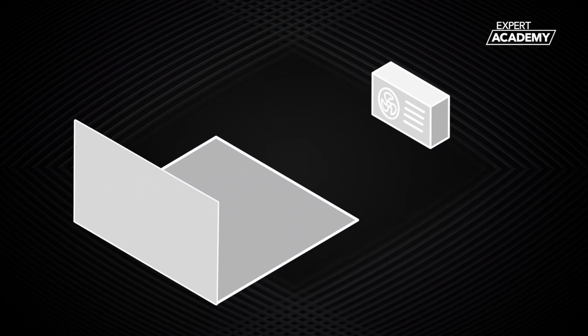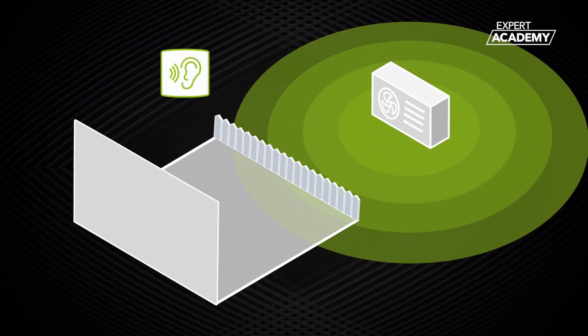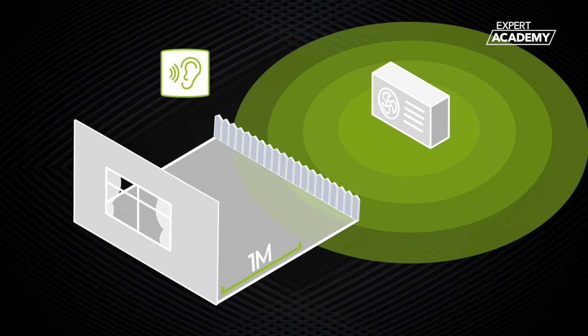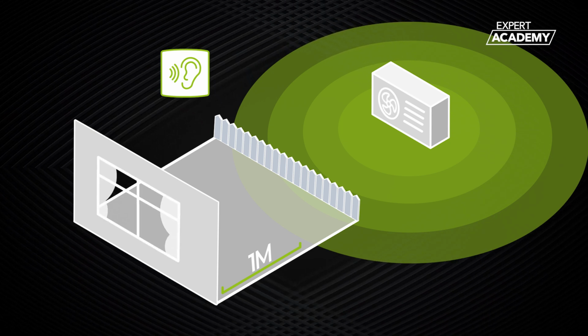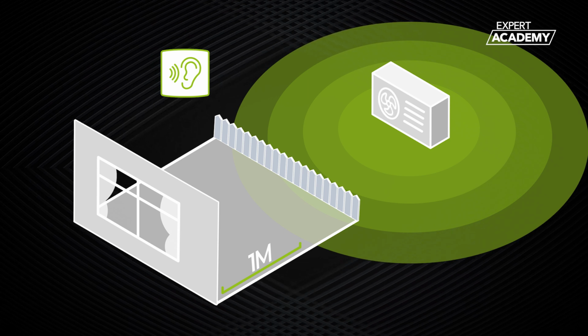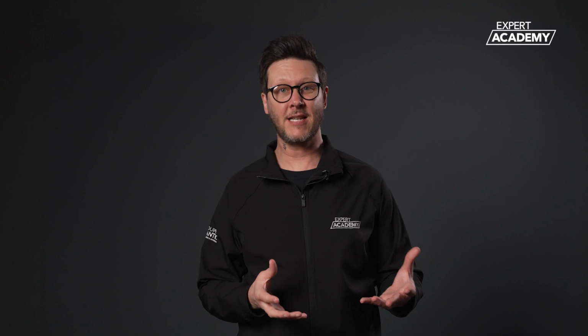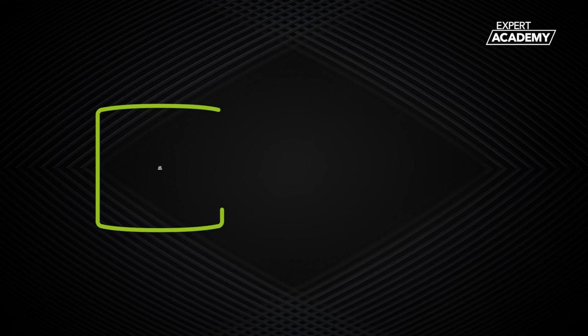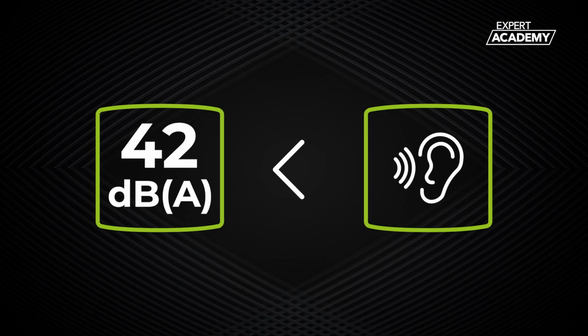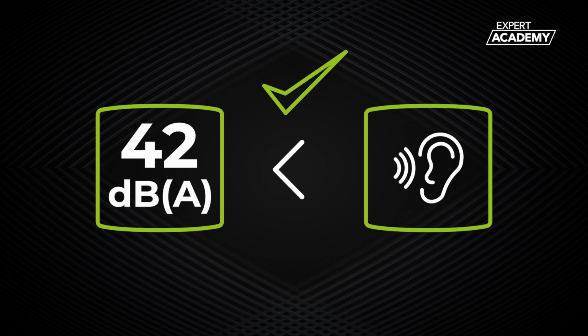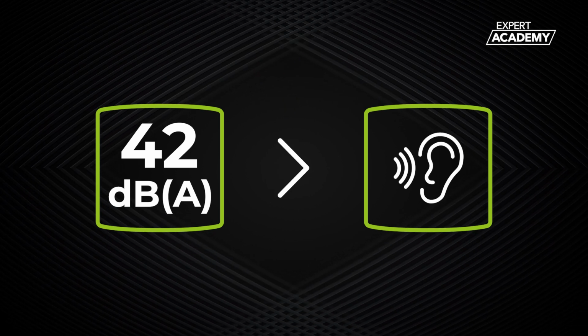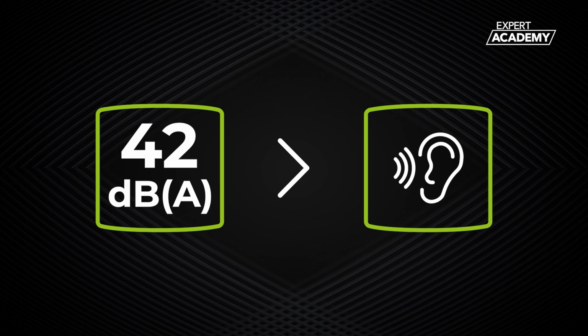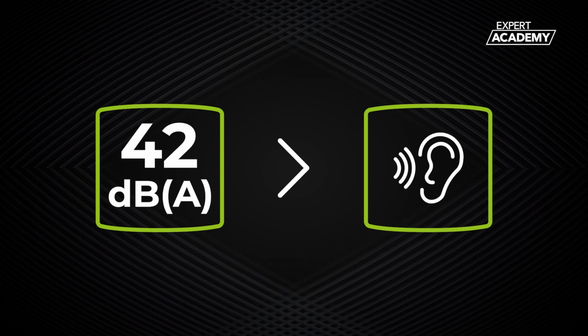This entails measuring a noise level of the heat pump from a distance of 1 metre from the nearest window or door of habitable rooms in neighbouring properties. This is known as the assessment position. There is a relatively simple 10-step process which will calculate the noise level from this assessment position. If the result is equal to or below 42 decibels, it will qualify as a permitted development. If the noise level exceeds 42 decibels, you may need to explore alternative installation locations or apply for planning permission.